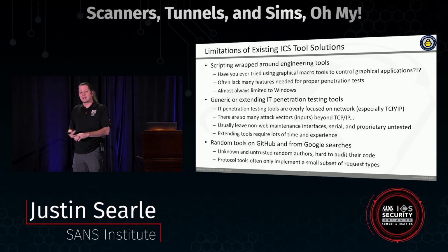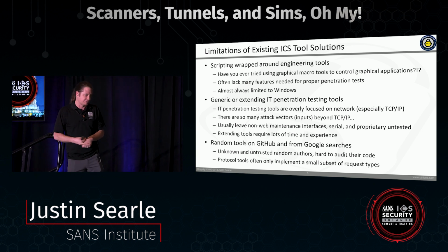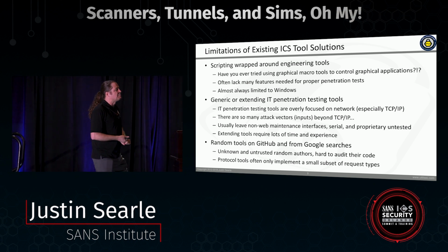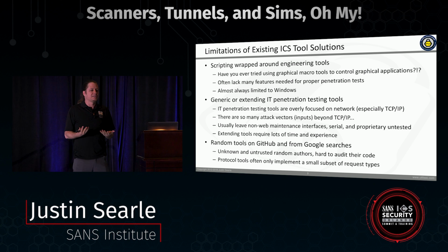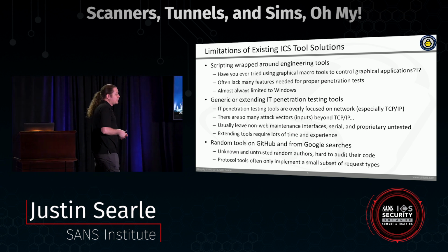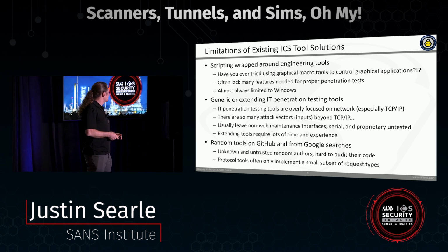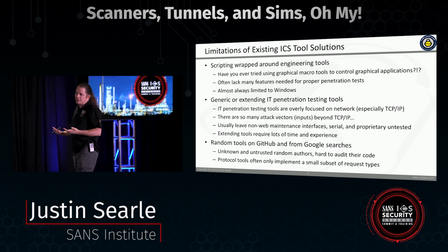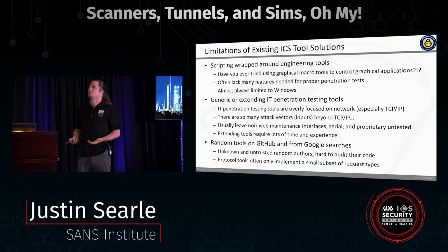And then what about everything that's not Ethernet-based? We have lots of serial-based connections, including fieldbus protocols and a myriad of different types of fieldbus protocols. We have proprietary maintenance interfaces and other types of interfaces that are proprietary hardware, proprietary wireless from our ICS vendors that we may want to test. So that becomes a bit of a challenge to try to do. And we have any other types of maintenance interface. It's just kind of like an endless list of what could be inside of some of these environments. So we can do it, but if that's all you're dependent upon and that's all you're using are the IT tools, you end up having some major gaping holes in your assessment methodology and in your final test once you're actually finished.